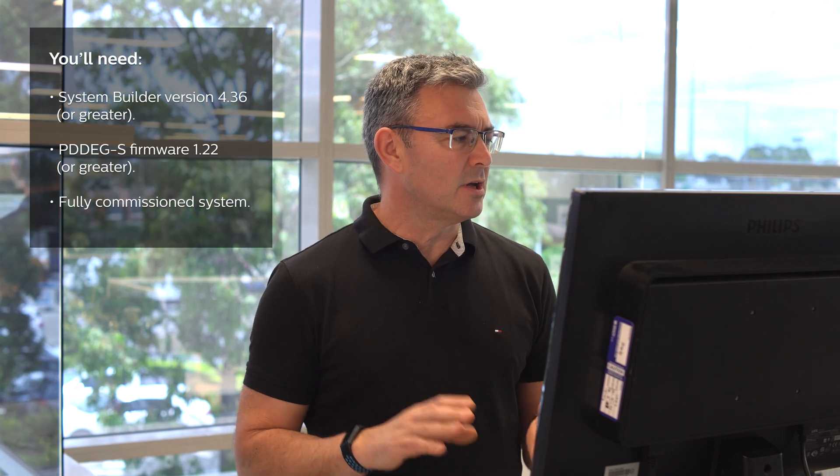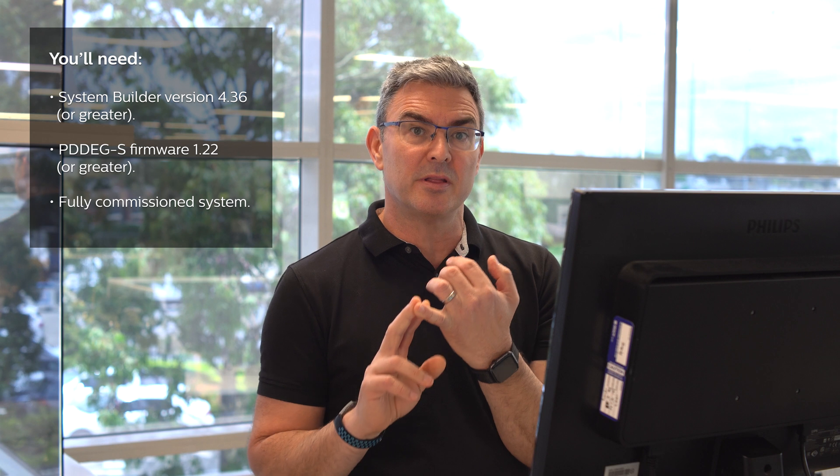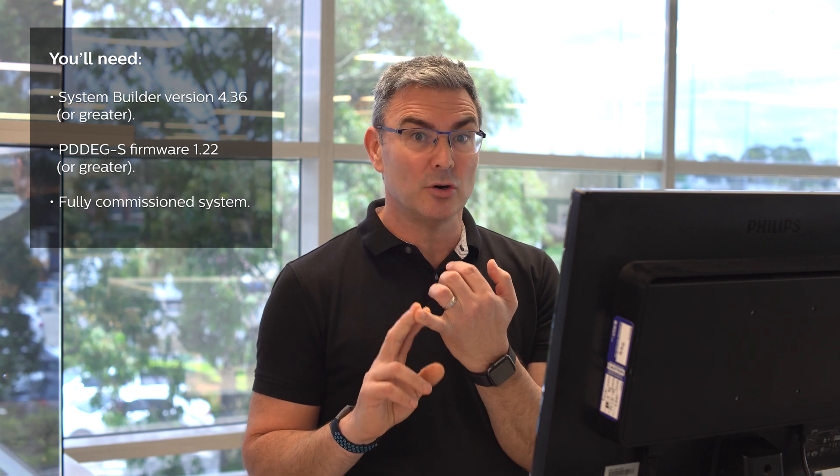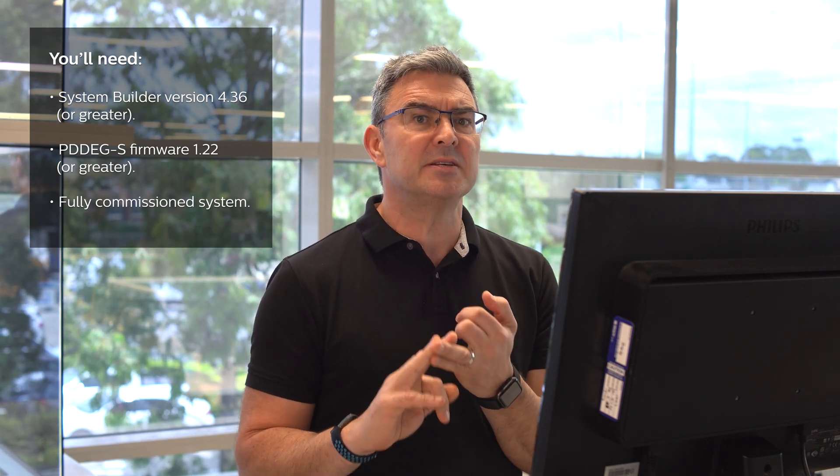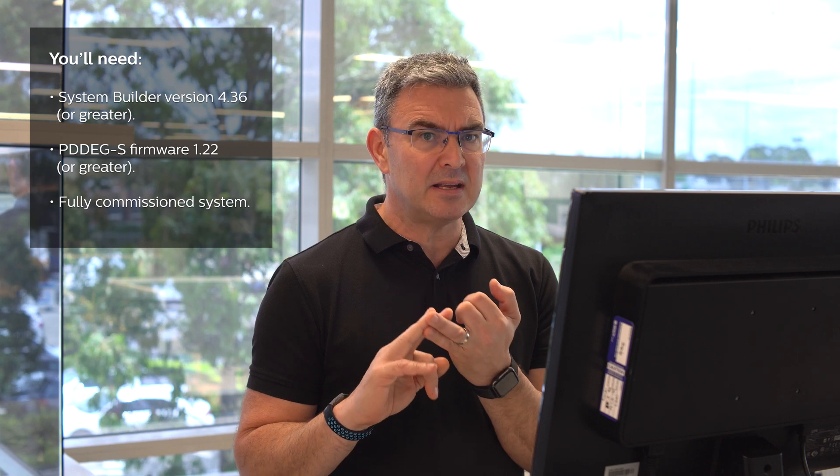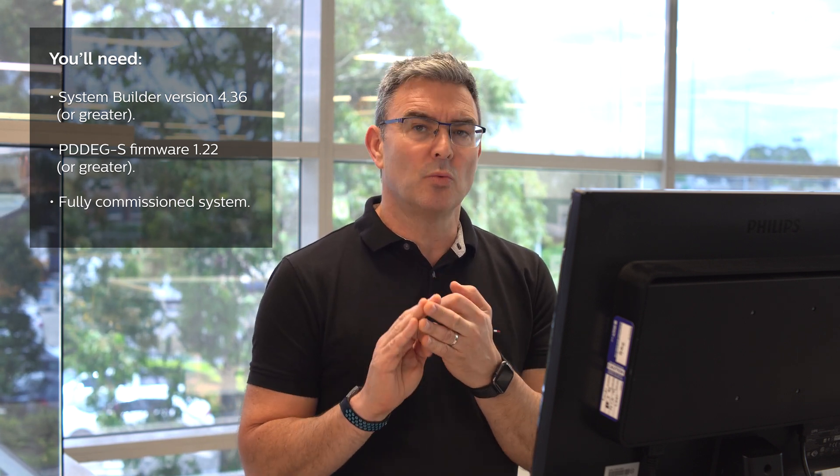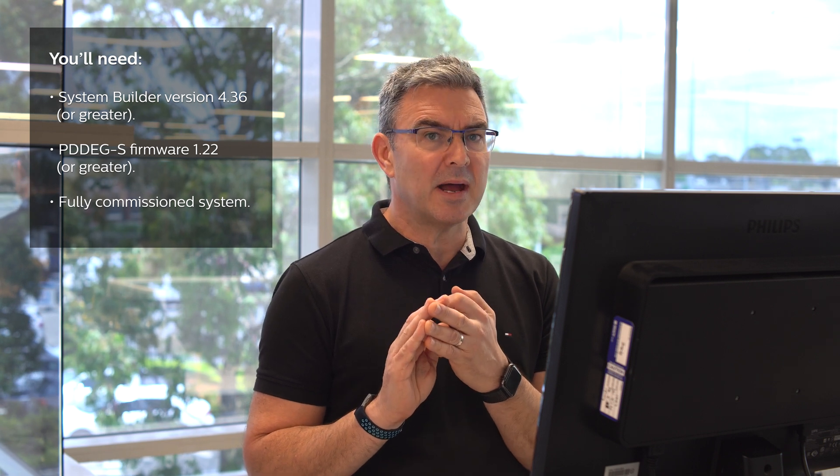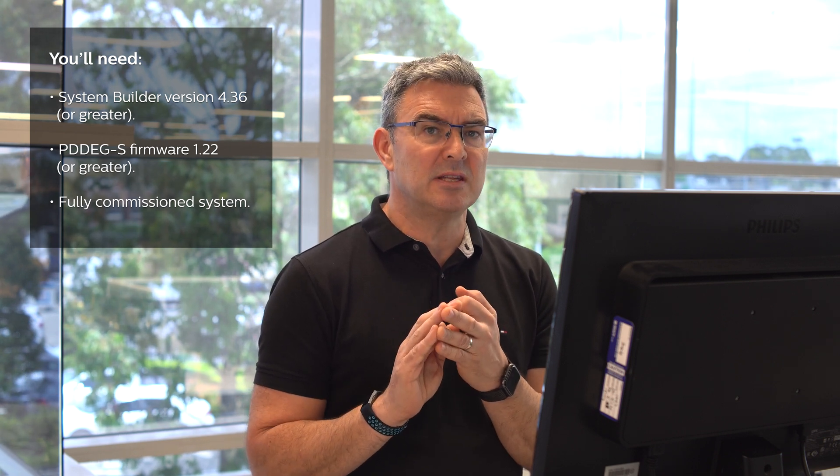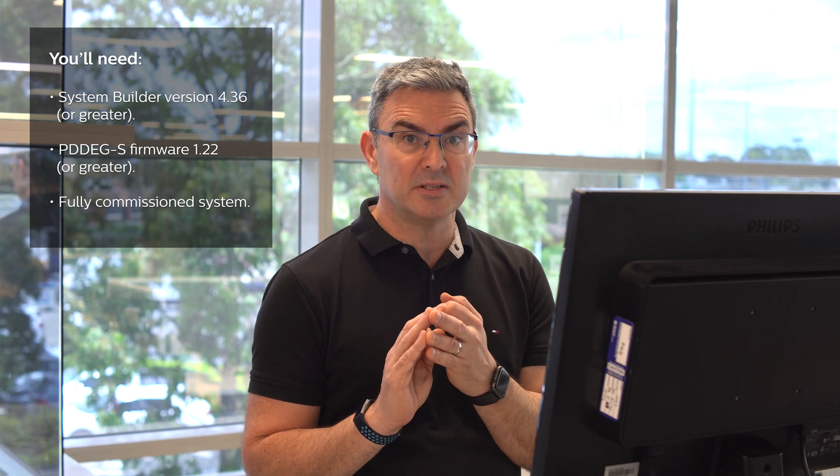So first things first before you start you need to make sure you've got system builder version 4.36 or greater, you've got firmware 1.22 or greater in your BACnet device and you have fully commissioned your system because the wizard that we're going to use to set up the BACnet will use your commissioning details to give you your points count. Once you can say yes to those three things then we can start with the setup.